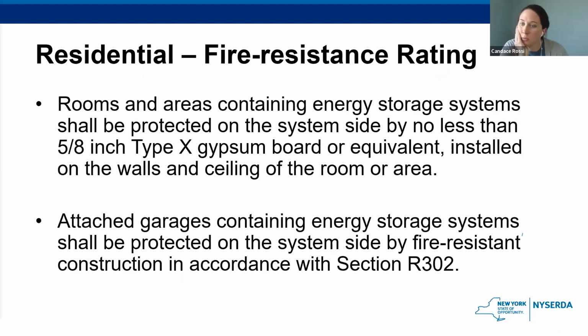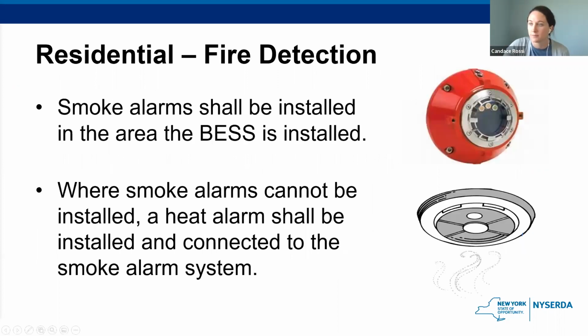So for clarification, the wall the system is installed on needs to be the 1 hour rated assembly, but not the rest of the space. So basically for residential, it will have to be at a minimum installed on the walls and ceilings of the room area. So I believe it only needs to be on the wall that the system's installed on for garage systems. But if it's in your home, the system needs to basically have the rated assembly for the entire space. And I'd also recommend reviewing the code to make sure that's in line with what you're also seeing.